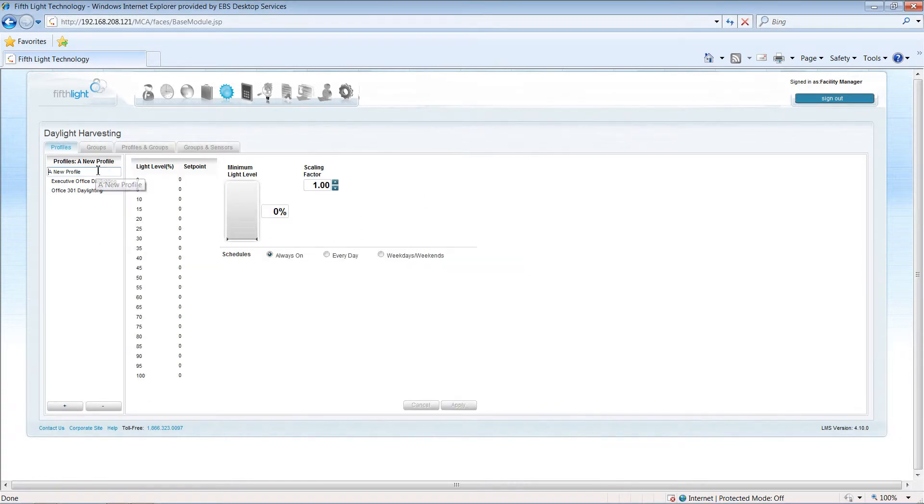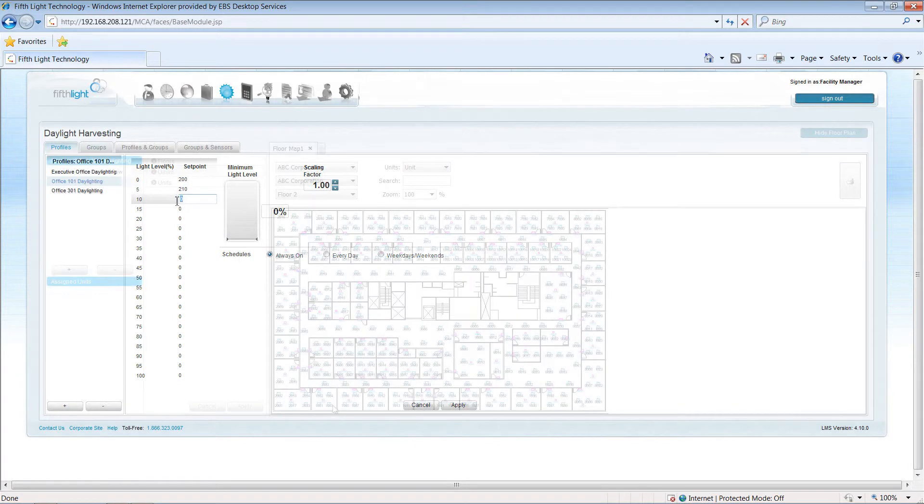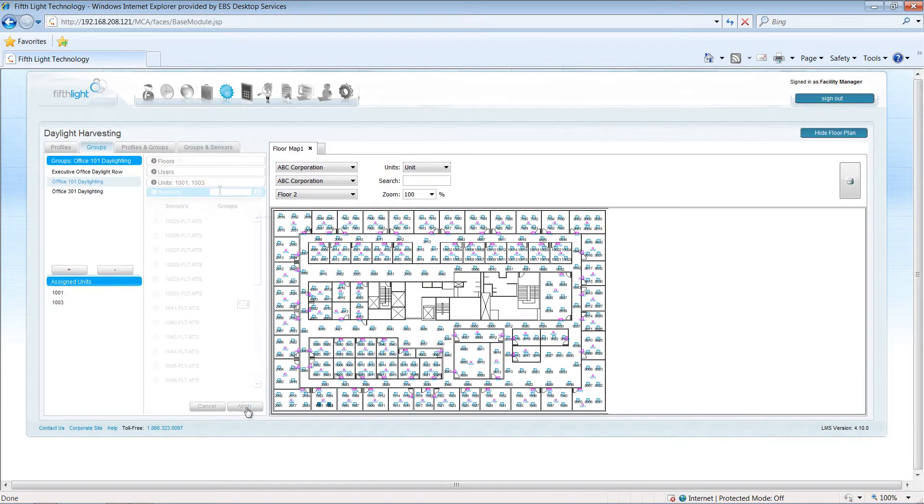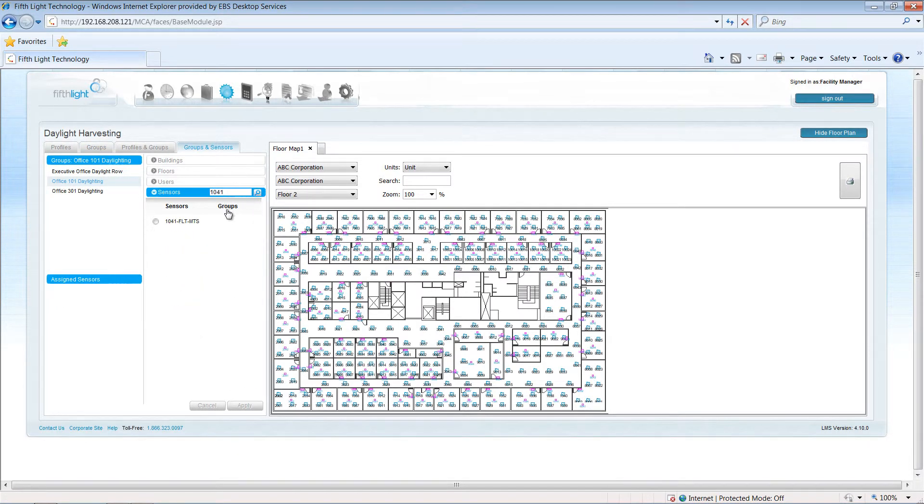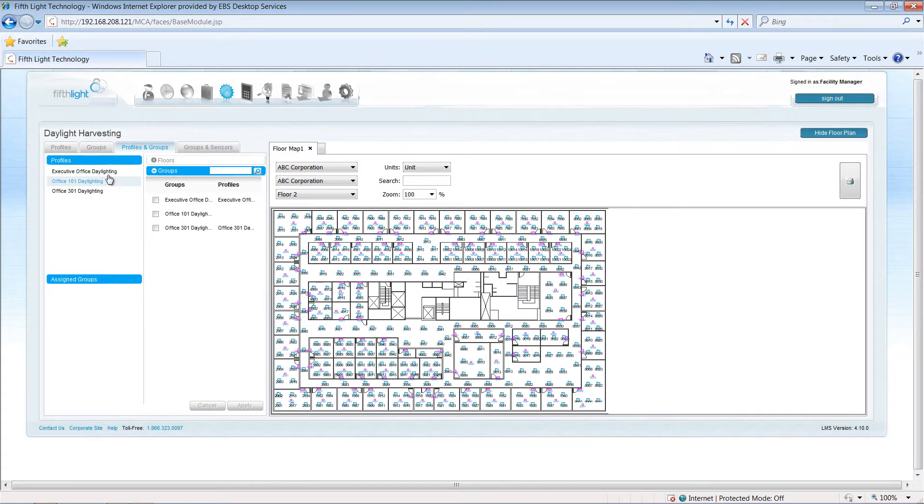During system setup, the commissioning technician will create the profile for each daylight sensor, defining the set points, creating the controlled lighting groups, and associating the group with a sensor. The profile is then applied to the group that needs to be controlled.